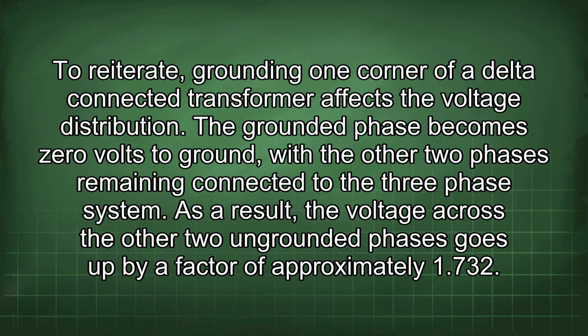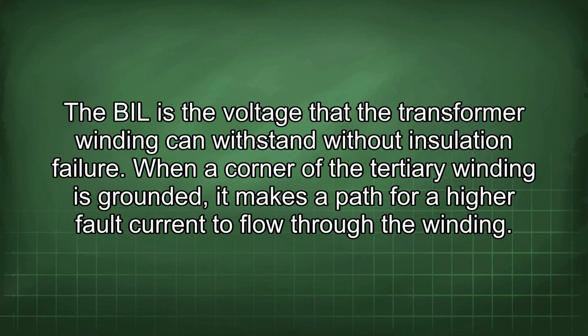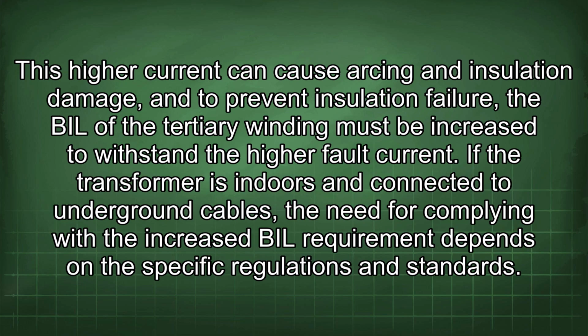To reiterate, grounding one corner of a delta-connected transformer affects the voltage distribution. The grounded phase becomes 0 volts to ground, with the other two phases remaining connected to the three-phase system. As a result, the voltage across the other two ungrounded phases goes up by a factor of approximately 1.732. The BIL is the voltage that the transformer winding can withstand without insulation failure. When a corner of the tertiary winding is grounded, it makes a path for a higher fault current to flow through the winding. This higher current can cause arcing and insulation damage, and to prevent insulation failure, the BIL of the tertiary winding must be increased to withstand the higher fault current.